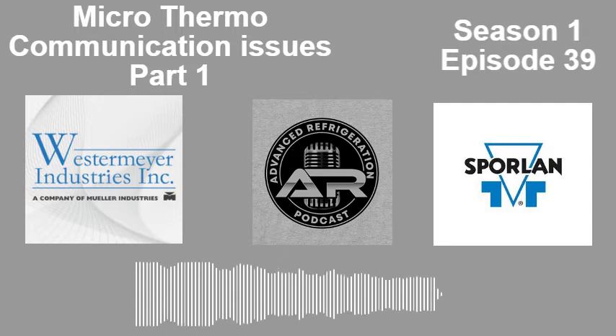A lot of people always say, Charlie, where do I put my EOL, my end of the line terminator? And that is not what we want to do with an Echelon channel. I don't like to call it a terminator because it puts people in mind that it's got to be end of line termination. I'd rather just say the resistor. You always try to look for the geographic middle of the channel, and that's where we want to land our resistor. So we have a resistor on the backbone.